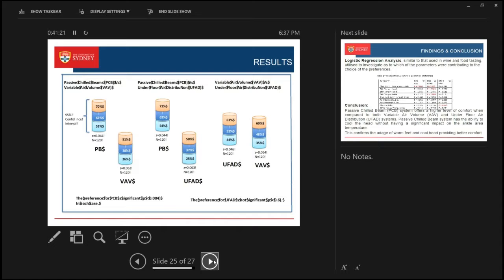But in terms of the active chill beam, the results that we got were not that different, except that they were closer to the VAV. The percentage wasn't as much as that, because the active chill beam, with the air system producing and supplying, is acting quite a lot as an air system, whereas passive is acting more as a convective side, with a bit of radiation.